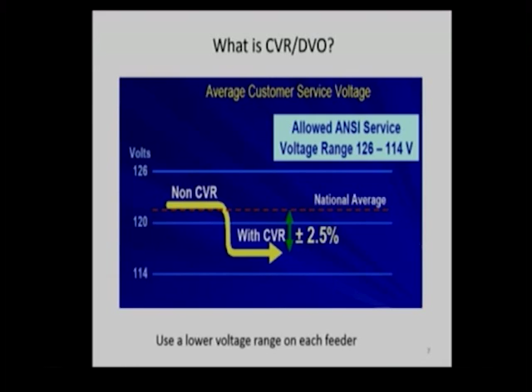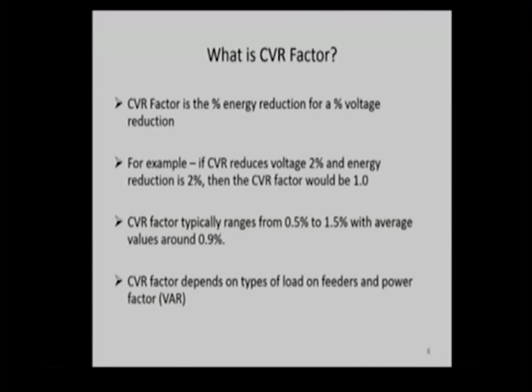One interesting issue is what's called the CVR factor. So if we reduce the voltage to the outlets by, say, 1%, how much energy savings do we get? And that depends on what the loads are and what type of equipment customers are using. It also depends on the time of year and other factors. But typically, you can almost get 1% energy reduction for every 1% of voltage reduction. And this has been seen in pilots and national standards or national studies by many people.